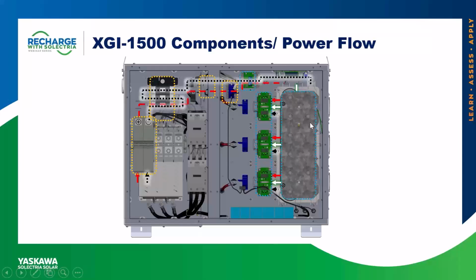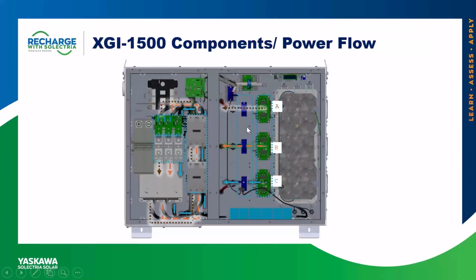From there, it goes directly to the DC filter capacitor banks. And from there, this is where the magic happens. We got our IGBTs. This is where the conversion from DC to AC is happening. So from here, it converts to AC. And then as you can see in the next slide, it passes through your current CTs for each phase.